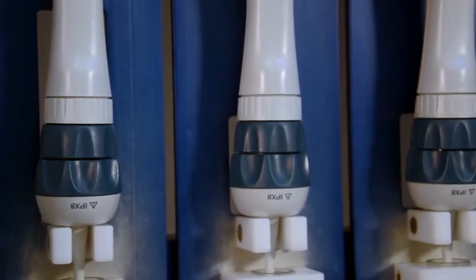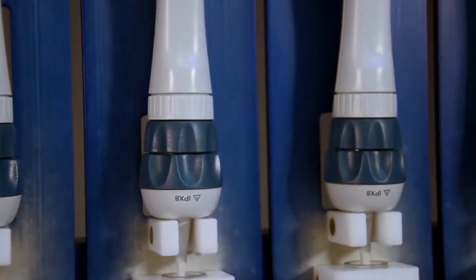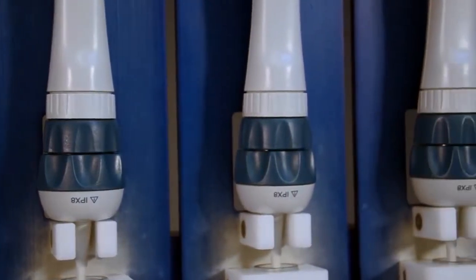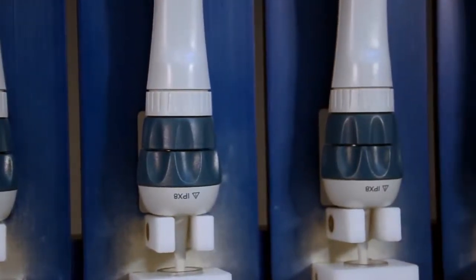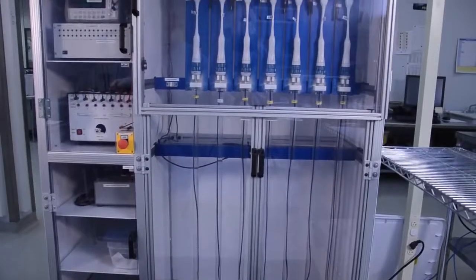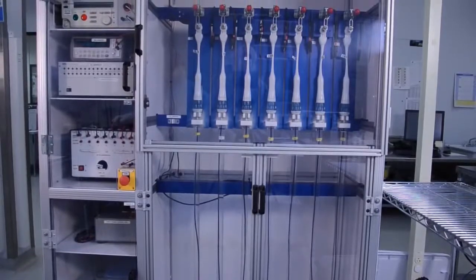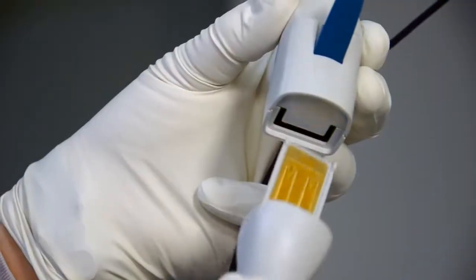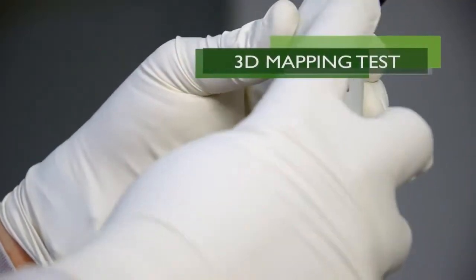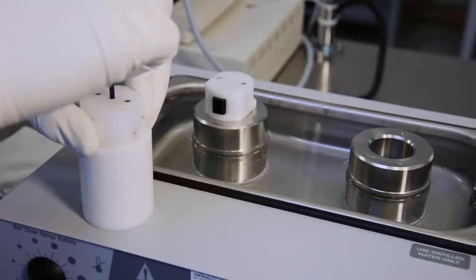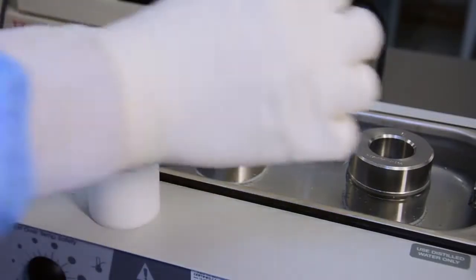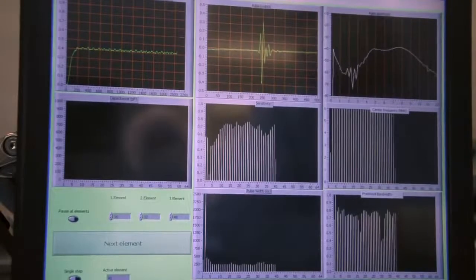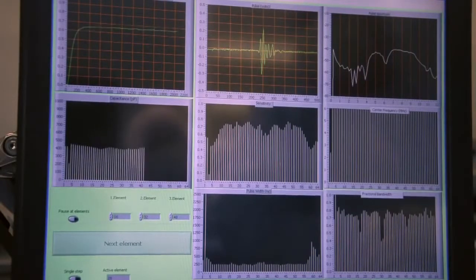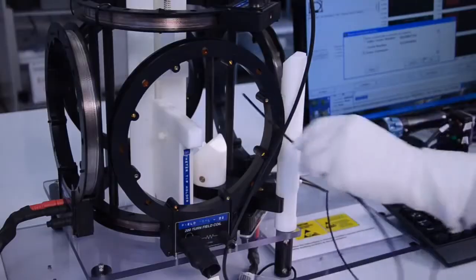For ultrasound catheters, function testing includes an assessment of ultrasound capabilities in addition to electrical safety testing. Stryker's proprietary testing system ensures that ultrasound components have not been compromised. 3D mapping capabilities are assessed by testing the tip of each catheter to confirm the integrity and accuracy of the location sensor. This sensor is responsible for transmitting the location of the catheter's tip while mapping the heart.